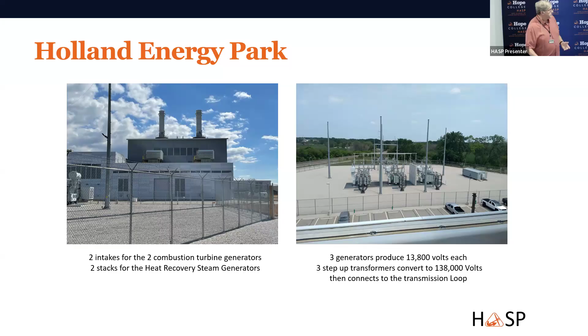What happens in the peak, in the summer when everybody's got their air conditioners running and the plants or factories are all running? So there are three other generators on the south side: two smaller ones, 35 megawatts, GE Frame 6Bs, and one larger one, 84 megawatts, in the back. From an EPA standpoint, they're licensed to run roughly 10% of the time, because most of the time they're not needed. So when they run is when we hit a peak in Holland, or we're having to do maintenance on Holland Energy Park, or the grid needs more electricity.